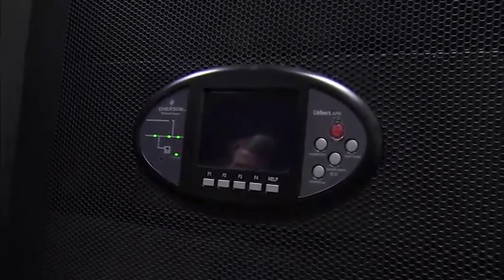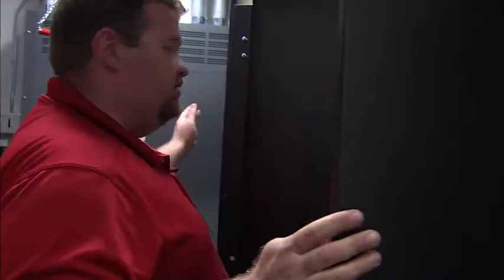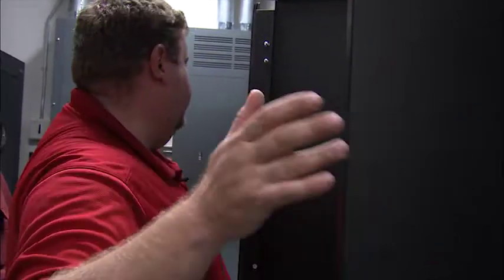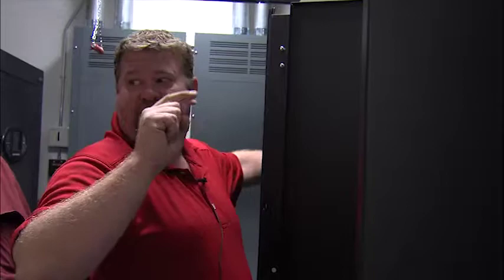So again, if there's a DC fault current, a fault on this, or we go over temperature, there's a number of different variables where this will trip. In this system, both will trip on a DC fault current or an EPO button. Temperature, they won't. So basically, if you came up and pushed this EPO button there, and do you have one on the wall? Okay. And we'll go over that. These two breakers would trip, and the input breaker would trip. This system would go down. This unit and this unit, if you push either one of those red buttons.